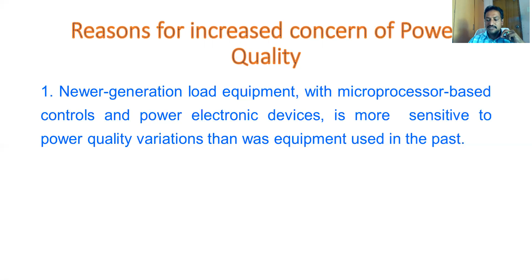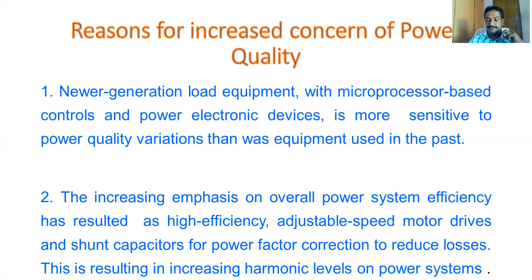Then the second is that you want to improve the efficiency of the power system. We are using adjustable speed motor drives also, because we want to control the speed. There we are using capacitors to improve the power factor and reduce losses. This results in increasing harmonic levels in the power system. So we should concentrate on this, and be concerned about power quality when we want to improve efficiency, maintain adjustable speed drives, or do power factor correction to reduce losses.